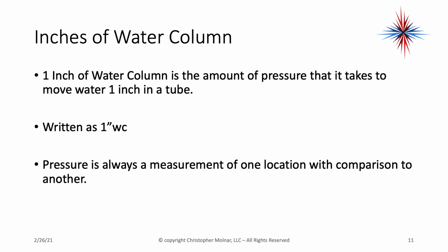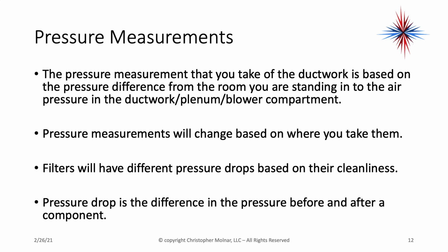Pressure is always a measurement of one location in comparison with another. So the pressure measurements you take of the ductwork are based on the pressure difference from the room you're standing in to the air pressure in the ductwork, plenum, or blower compartment. Pressure measurements will change based on where you take them. Filters have different pressure drops based on their cleanliness. A pressure drop is the difference in pressure before and after a component. Coils, your air conditioning coils, heaters, hot water coils, anything in the ductwork has a pressure drop. It changes the air pressure, and it's basically a resistance to movement.